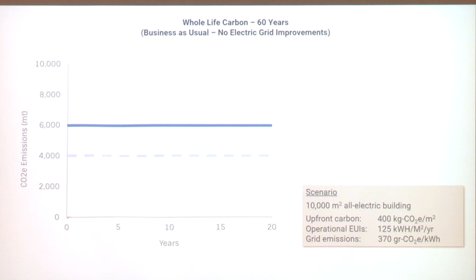Your upfront carbon is 400 times 10,000 square meters, giving 4,000 tons of carbon upfront. That's your upfront embodied carbon. Then, because of the replacement cycle in the MEP equipment, you get your total life embodied carbon. At 125 kilowatt hour per square meter per year, operational carbon rises over 20 years. This is the first 20 years, so you replace the MEP equipment only once.